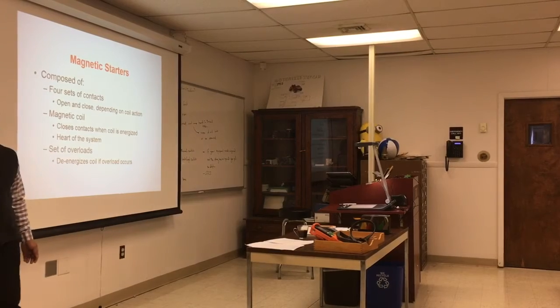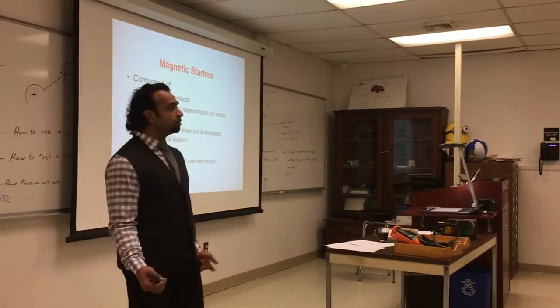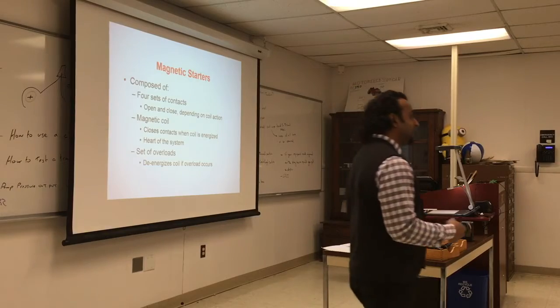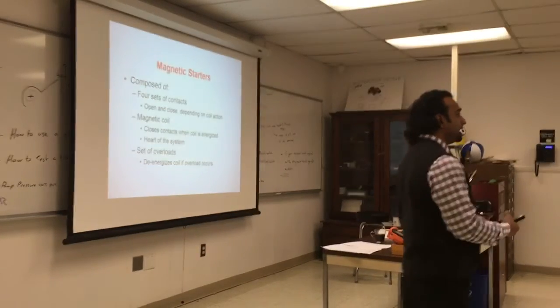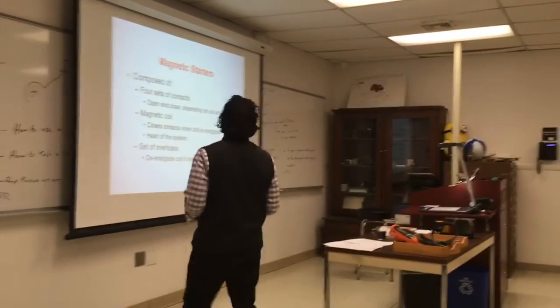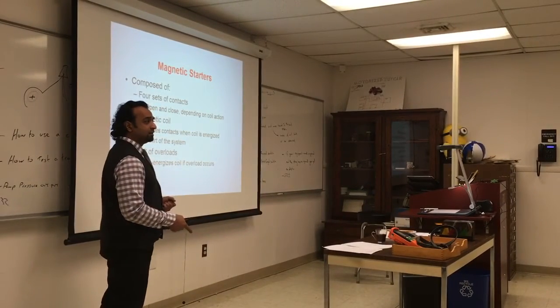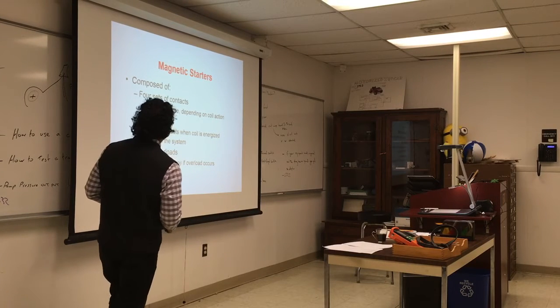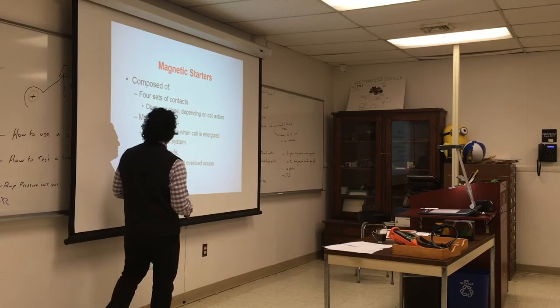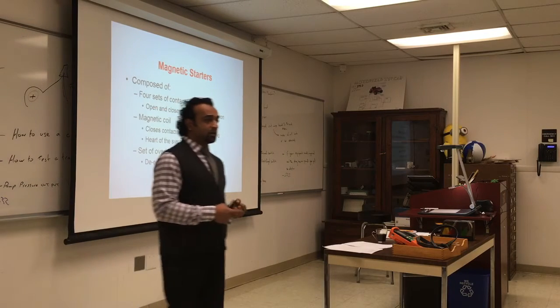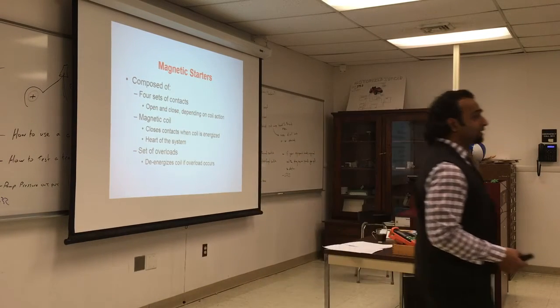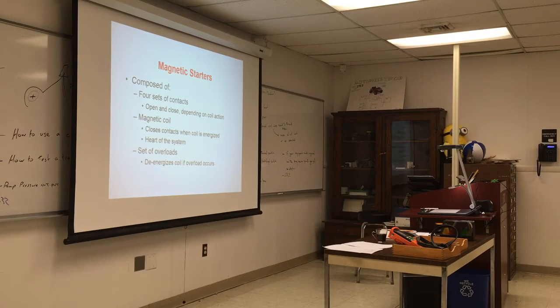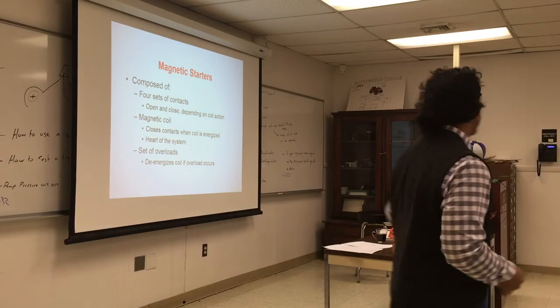Magnetic starter, we talked about that. What is a magnetic starter? It's a contactor with overload protection. It has an overload, meaning it has contacts that will break, and it has a coil that will draw the contact. There are four sets of contacts, open and close, depending on coil action, and there's a magnetic coil. It closes the contacts when the coil is energized. It is the heart of the system, mostly for compressors, so you will find magnetic starters on big central ACs.